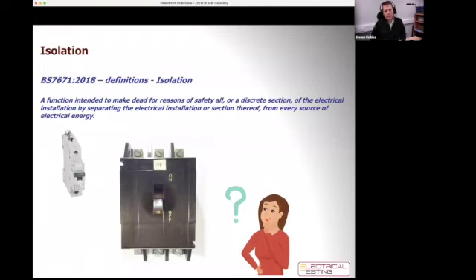BS 7671, the wiring regulations, clearly has a definition for isolation as well. Its definition says: a function intended to make dead, for reasons of safety, all or a discrete section of the electrical installation by separating the electrical installation from every source of electrical energy. So we've got terms like electrical energy and electrical charge, but in essence, we're going to be separating the part of the installation we want to work on from any other electrical charge or electrical energy that could come into contact with it.